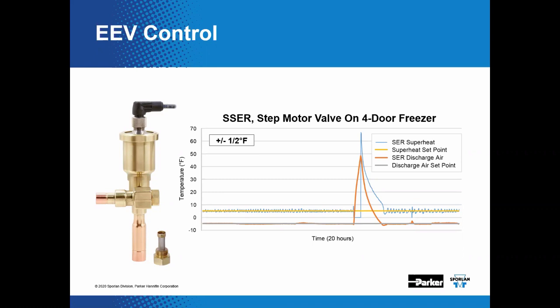Now, we've included a little bit of detail on a particular SSER step motor valve option. It has the neat little 3427 inlet strainer fitted to it. That's a nice little option because contamination is the culprit of almost all of our products. The only things that really belong in a refrigeration system are refrigerant and oil. Well, okay. I kind of like lubricant, but yeah, oil, lubricant. Okay, lubricant. Yeah, this helps. It's an aid to help keep some of the hammer handles and lunch boxes out of the workings of this valve. True. And maybe even a few copper shavings and a little bit of copper oxide and things like that. Could be a good thing.